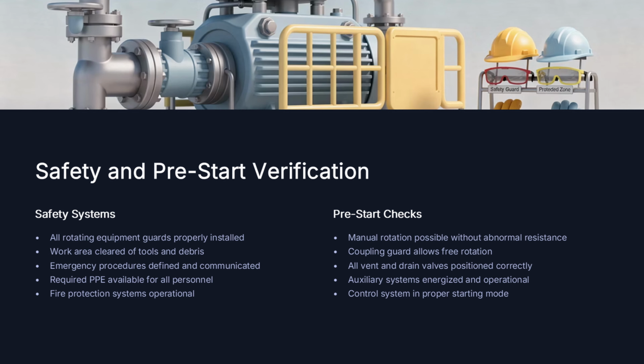Next, safety and pre-start verification. Now we arrive at the final gate before startup: safety. Every rotating guard must be installed, clean, tools removed, debris cleared, emergency procedures communicated, required PPE available, fire protection systems ready. Then comes the final pre-start check: manual rotation, correct valve positions, auxiliary systems energized, control systems prepared. These checks may seem simple, but simple checks prevent serious incidents, and experienced commissioning engineers know something important. The final 5 minutes before startup often determine the next 5 days of troubleshooting.